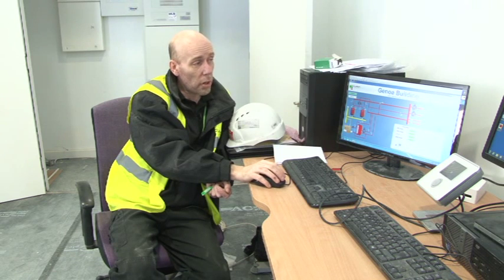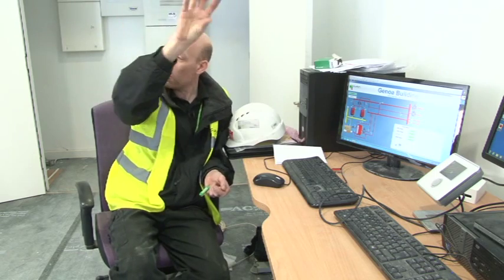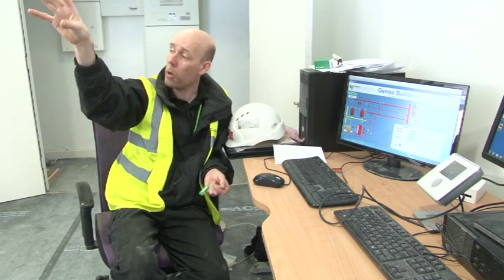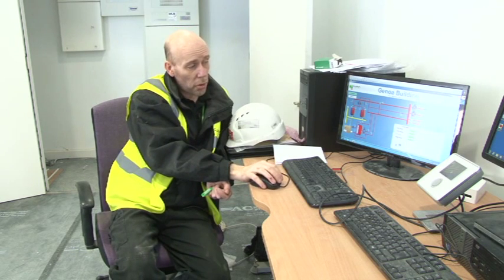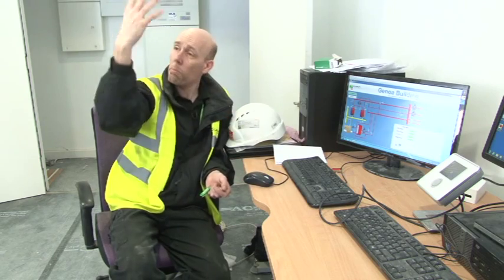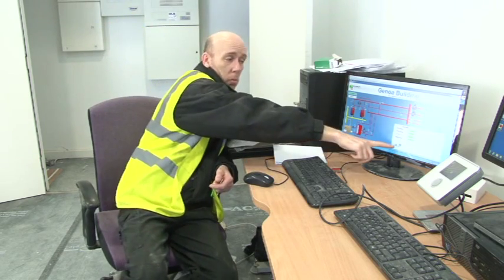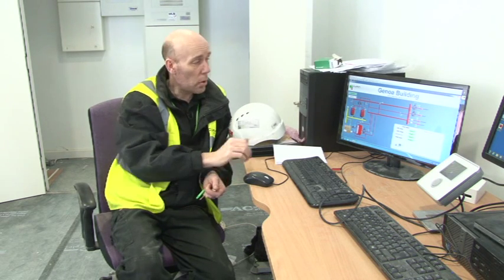Again, on here it will tell you which of the 2 pumps is running. So on this one it tells us that pump number 1 is running and pump number 2 is stopped at the moment, not running. So it gives the same with the red and green lights on the panel, or the green light and no green light. You get the same indication. Same with the flue fan, the fan in the plant room that's bringing fresh air into the plant room. We have an indication that the fan is running to show that the fan is enabled, etc.